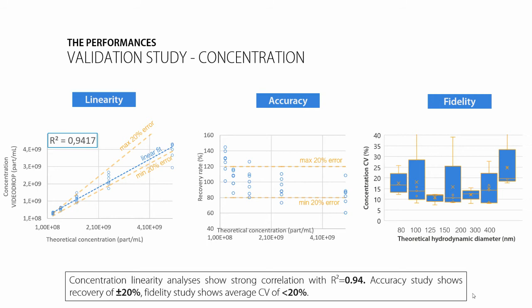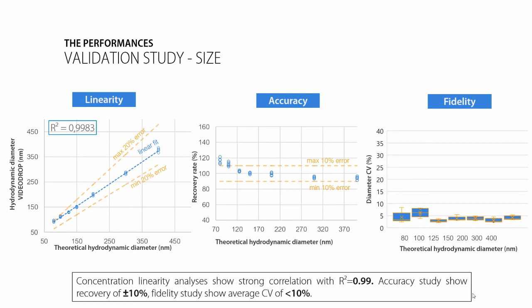On this slide, you can see the result for the size determination. Within the standard protocol defined internally, the identified linear range is between 80 nanometers and 400 nanometers. The accuracy shows a good recovery within a mean of 10%. It is needed to note that the small particles can be slightly overestimated. The fidelity study showed an average coefficient of variation under 10%, which is very reproducible.